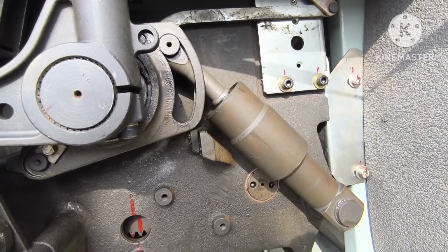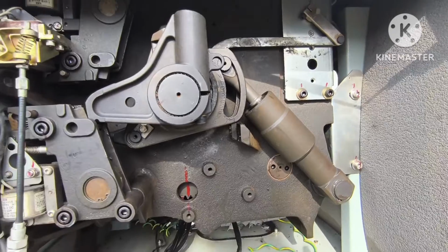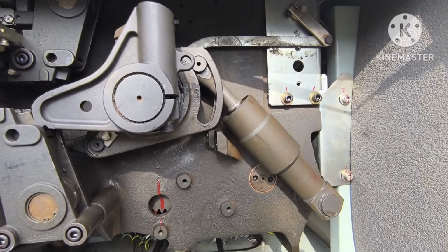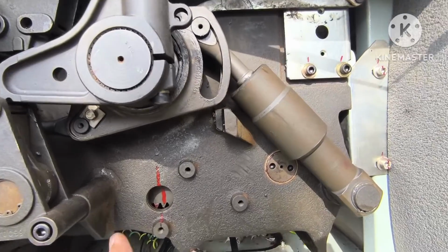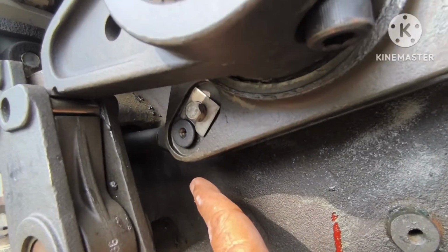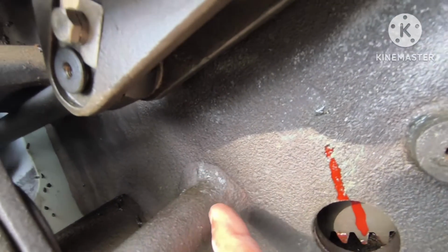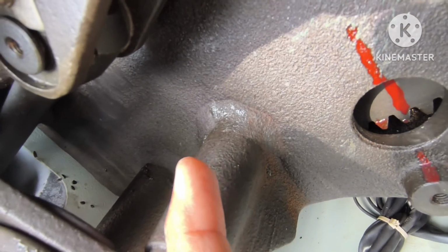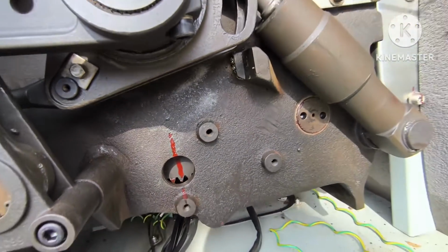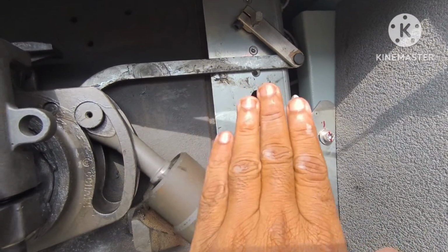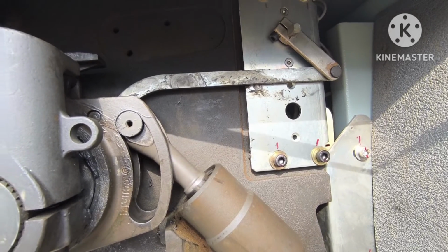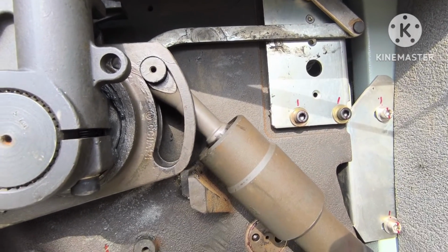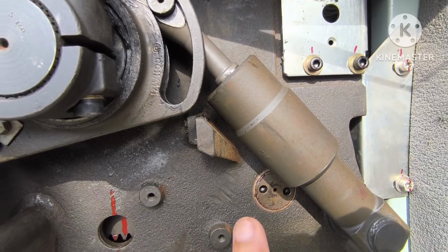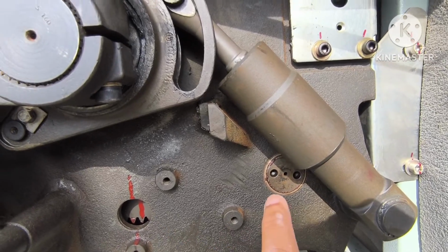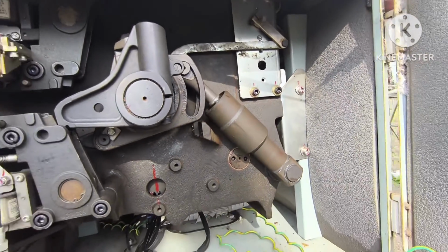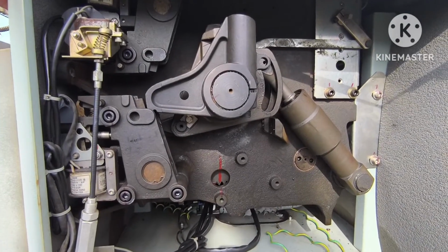This is called the dashpot. Its function is to slow down the final phase of the opening operation. This is called the dashpot. And all the mechanism here is connected internally. It is not so clearly visible, but I will show you once. Here it is connected through that tripping spring. So inside, the NO NC contact will be there, that is 12 NO, 12 NC contact will be there. Inside, a spiral type closing spring will be there, and also the closing spring charging motor will be there. The spring charging motor, closing spring, and the auxiliary contact will be there inside this. So this is the mechanism inside these breakers.